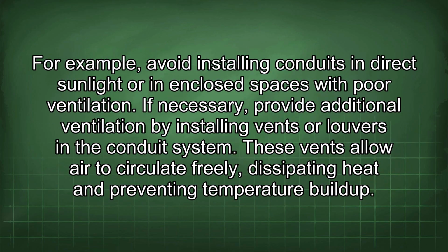For example, avoid installing conduits in direct sunlight or in enclosed spaces with poor ventilation. If necessary, provide additional ventilation by installing vents or louvers in the conduit system. These vents allow air to circulate freely, dissipating heat and preventing temperature buildup.